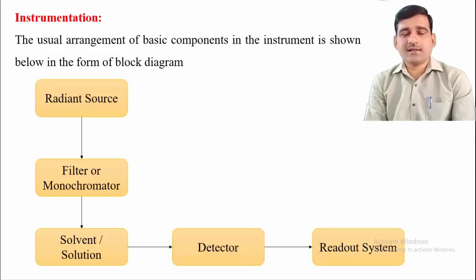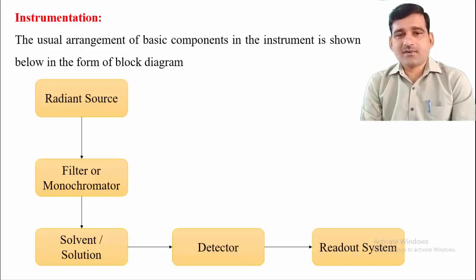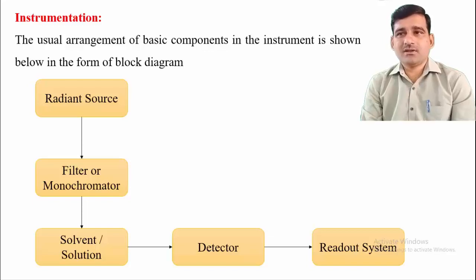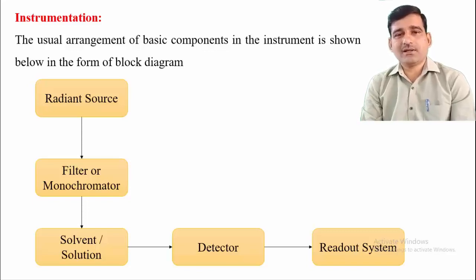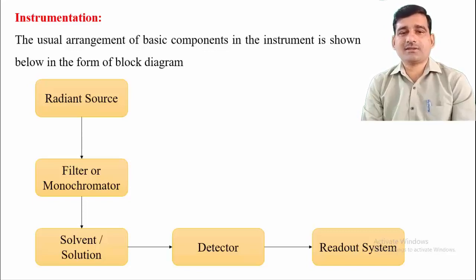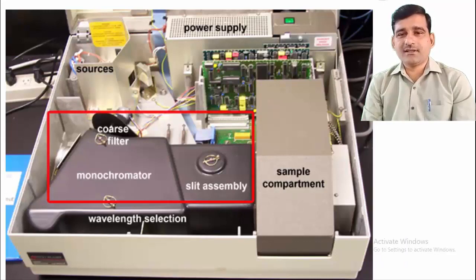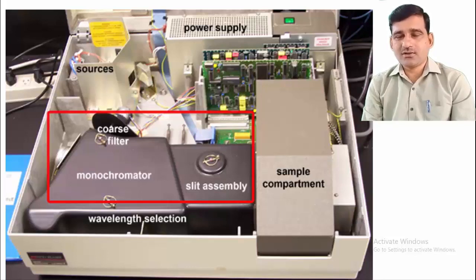Finally, the signal goes to the readout system, which gives the output in terms of a chart or digital signals showing how much light is absorbed and how much is transmitted by the sample solution. This is the block diagram of the spectrophotometer, which generally has five basic components: radiant source, filters or monochromators, solvent or solution compartment (sample cell), detector, and readout system.